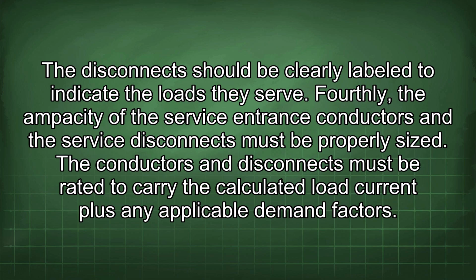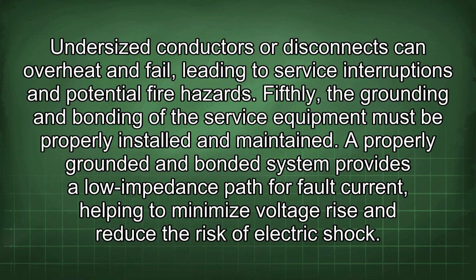Fourthly, the ampacity of the service entrance conductors and the service disconnects must be properly sized. The conductors and disconnects must be rated to carry the calculated load current plus any applicable demand factors. Undersized conductors or disconnects can overheat and fail, leading to service interruptions and potential fire hazards.